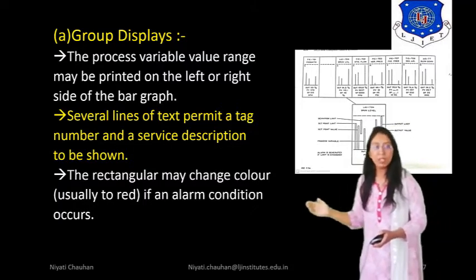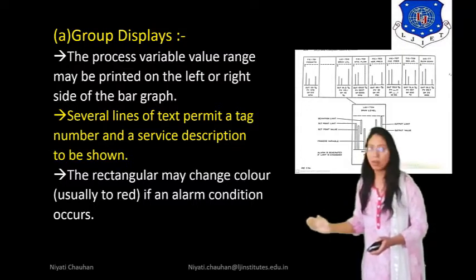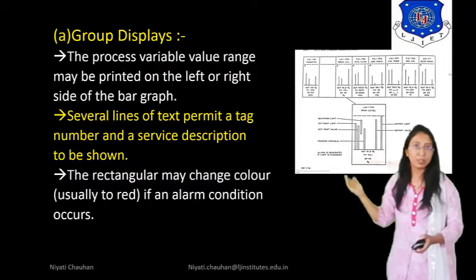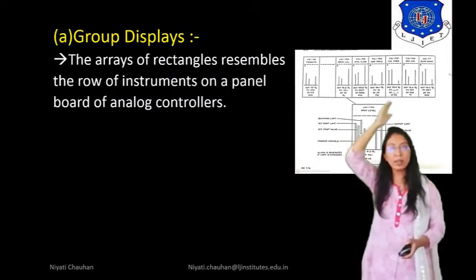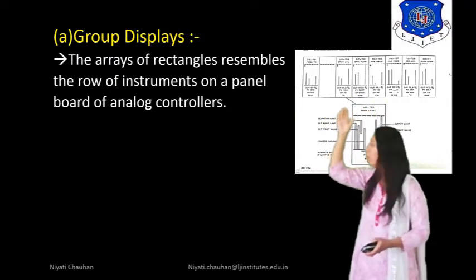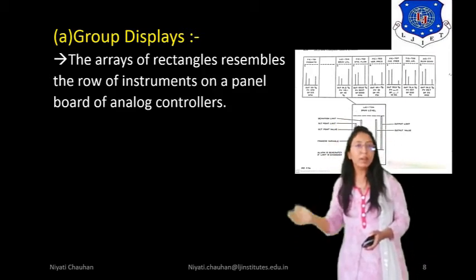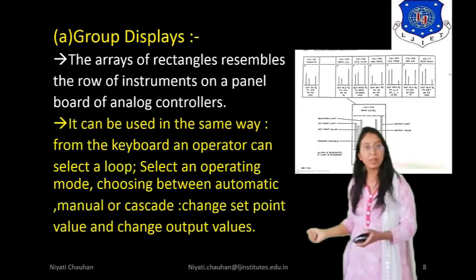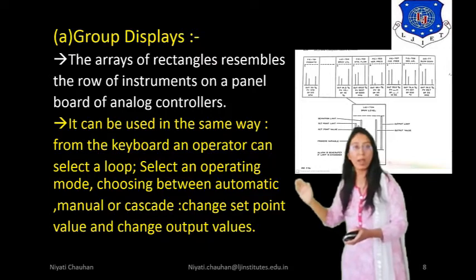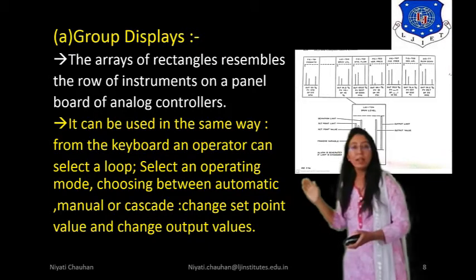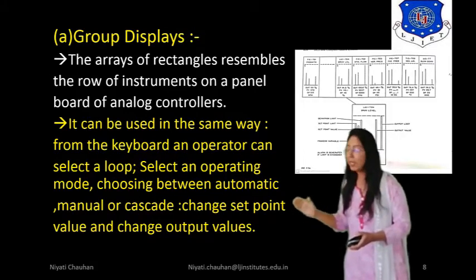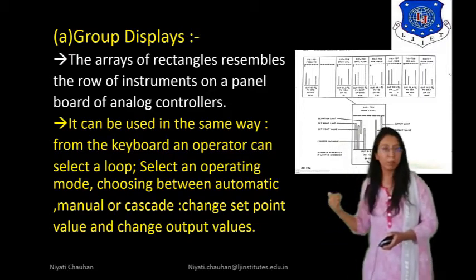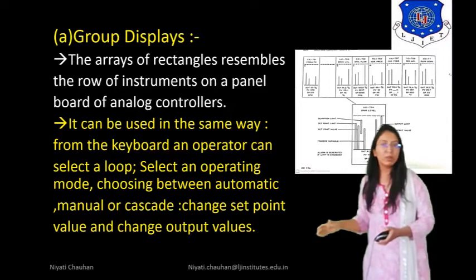The rectangle may change color — usually to red — if an alarm condition occurs. The array of rectangles resembles the row of instruments on a panel board of analog controllers. We can rearrange our process variables and change their order as required. From the keyboard, an operator can select a loop, select an operating mode choosing between automatic, manual, or cascade, and change the set point value and output values.